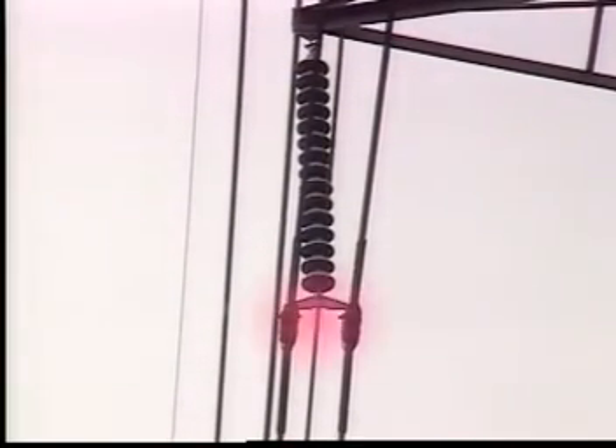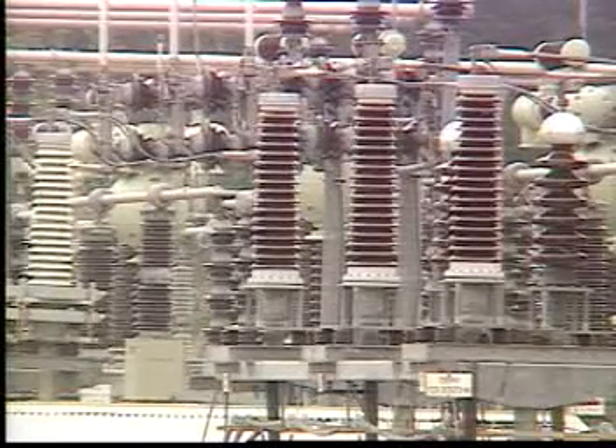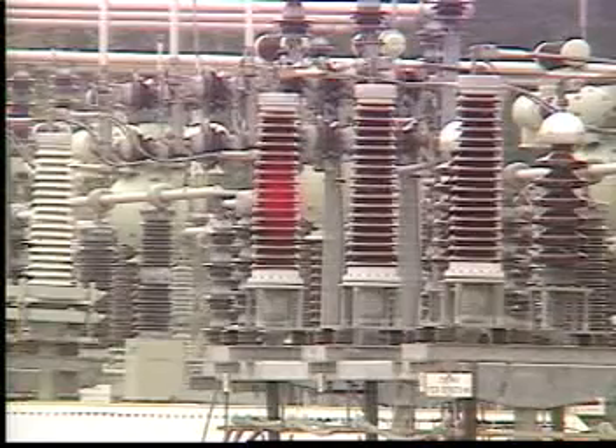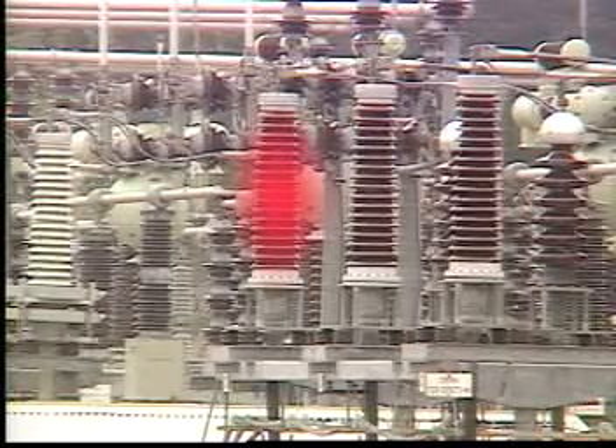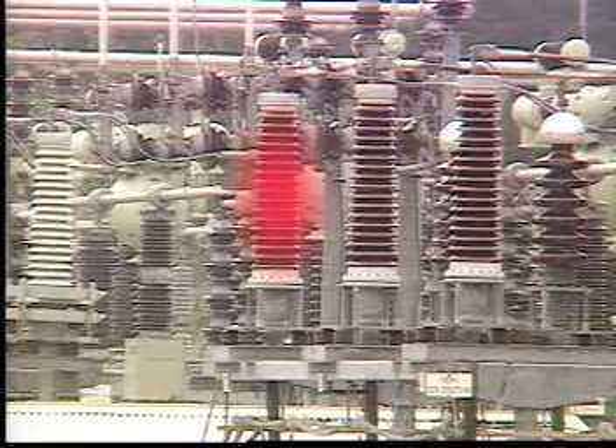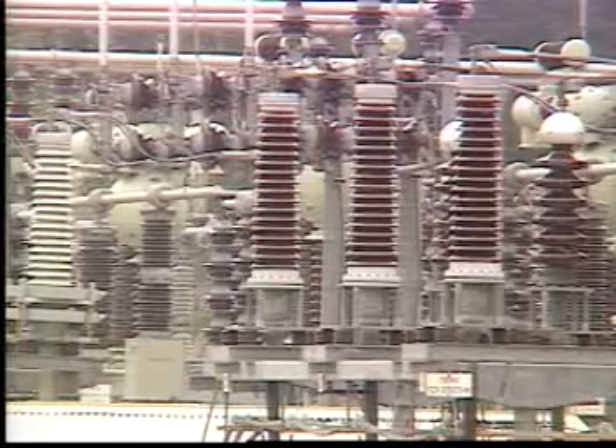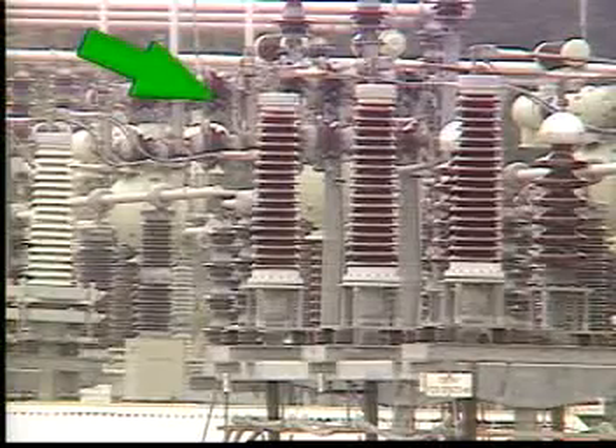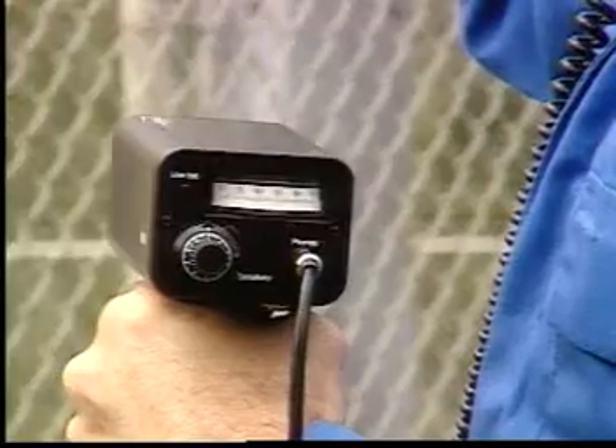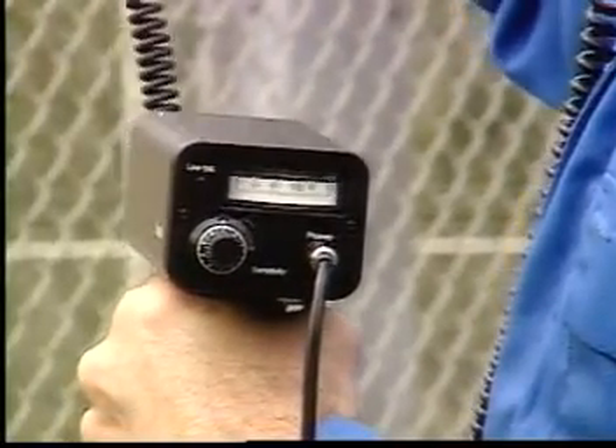However, not all electrical discharge is destructive. Non-destructive or nuisance corona may result if there are sharp points or edges on the conductors of high-voltage lines. Electrons may jump off these points, especially in humid weather. Similarly, insulators that have cracked or broken bells may have surface tracking over the broken areas and corona from the sharp edges. This may not be a serious problem. It may be explained by sharp edges, burrs, or points at the ends of the insulators, which can give off a nuisance electron spray. Using ultrasound, we're able to distinguish between these sounds.